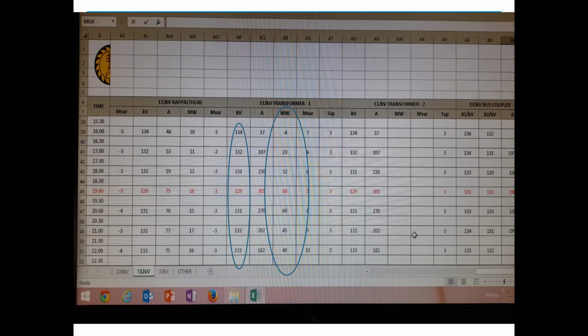So we can see this type of fluctuation throughout the day, even in transmission networks at the moment. You can also observe the voltage values. Around 4 o'clock, on the 132 kV lines, you can see the voltage as 134 kV. And at the peak time at 7 o'clock in the evening it is 129 kV. So this is the nature even in the transmission network at the moment.